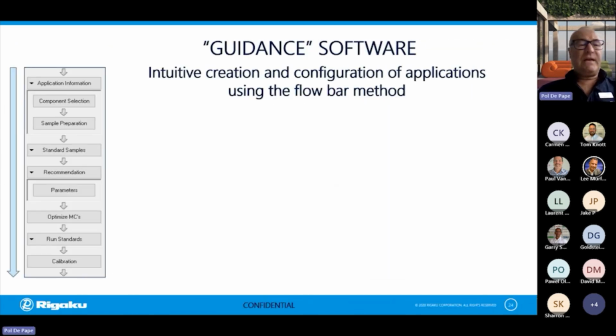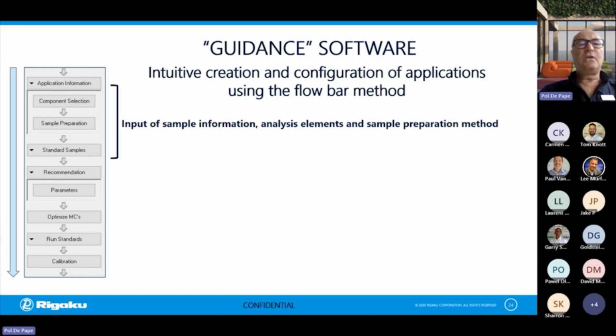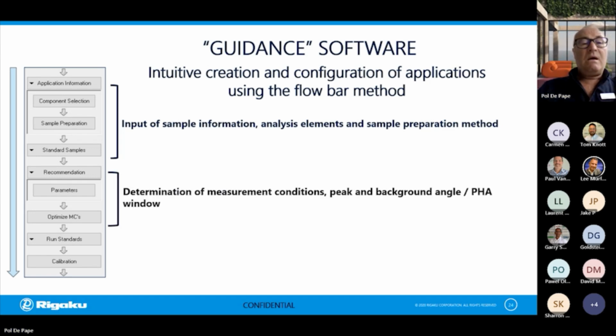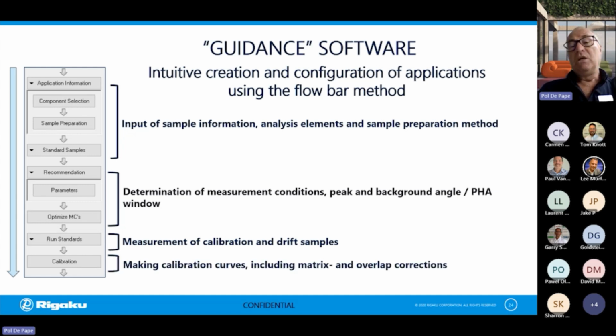The guidance software is very intuitive. If you want to make a calibration, for example, we see a flow bar method. We go from top to bottom. The first part is putting in all the information you have about your sample: elements you want to analyze, sample preparation methods, concentrations. After that, we define the measurement conditions, define peak and background angles, perform PHA analysis, and then we can run our standards and drift correction samples, and then we can make the calibration curves. So for someone who has really no experience, the only thing you basically have to do is fill in the sample information, and then you can just scroll down through this flow bar, and at the end, you will get the calibrations automatically done.